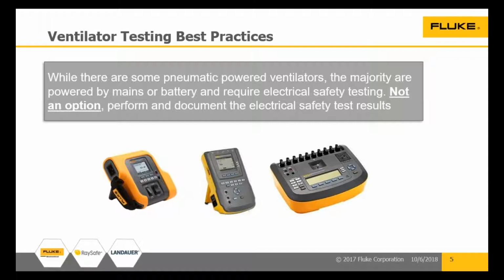Your pass-fail criteria is already specified in NFPA 99, so you can determine it yourself, or on some test instruments you select the standard you're going to use, and it will automatically give you the pass-fail criteria. That's even better—now you're objective, not subjective. The rule I've grown up with in this 40-year career has been independent, objective evidence of minimum performance and safety in terms of medical equipment.